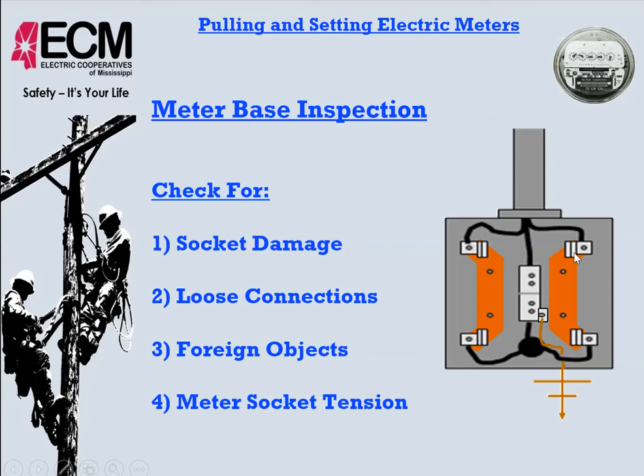Now typically we don't hook these up on an overhead meter base situation, the line or the load side. Now sometimes on an underground installation we do hook up the line side because we're running the wire to that. And then definitely there we want to make sure that we take proper precautions not to over tighten, under tighten, and also not to break the insulators, the plastic insulators. But also knowing that that is a possibility, we need to inspect that and be sure that they're not. Typically we will not be made aware of that when we're setting a meter because everything plugs in and the forces are against the back of the meter base.